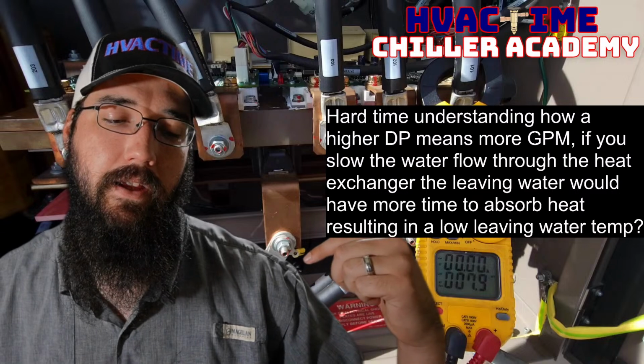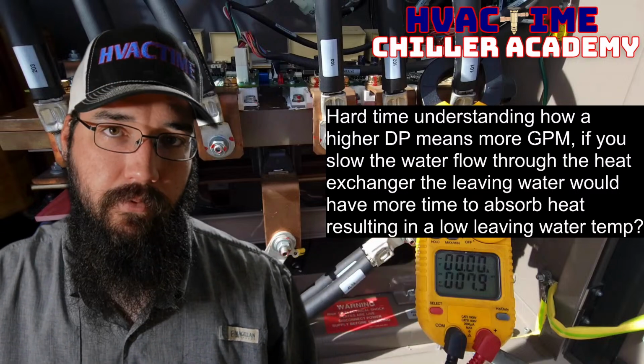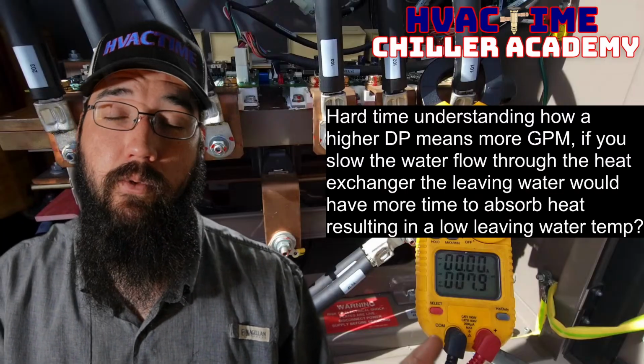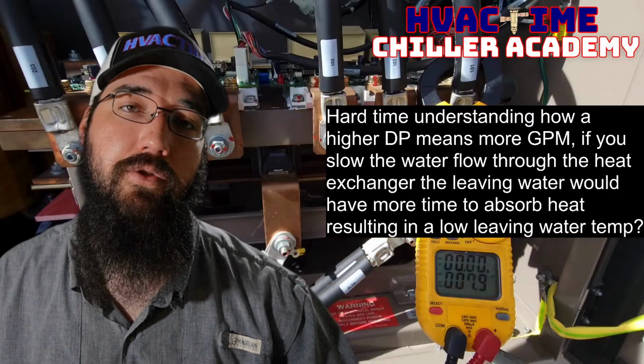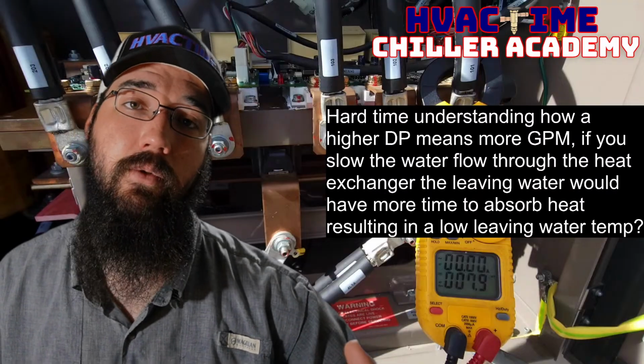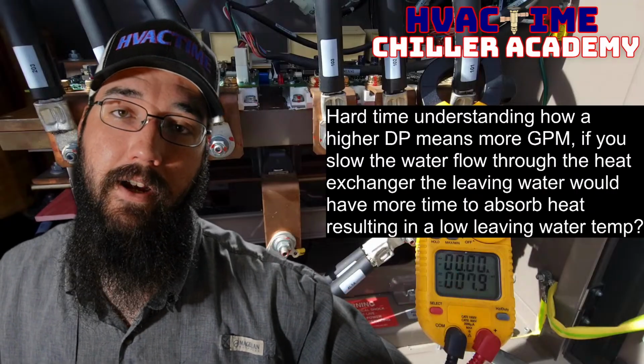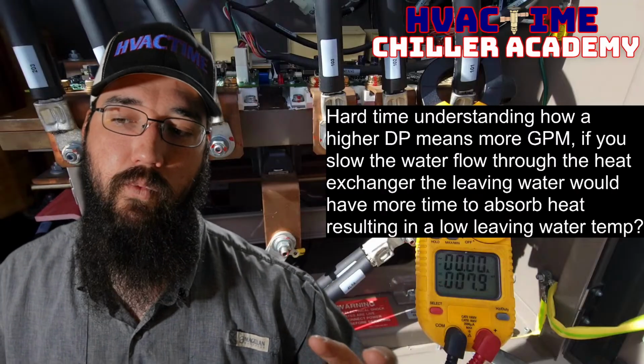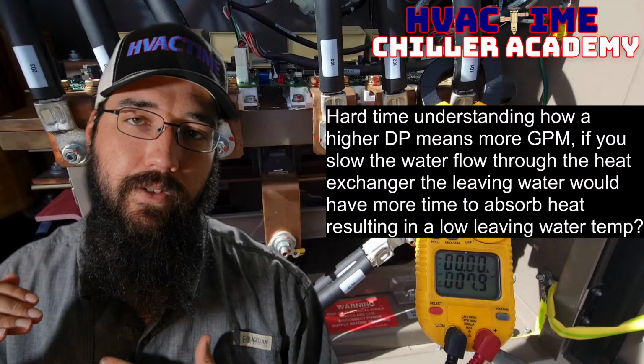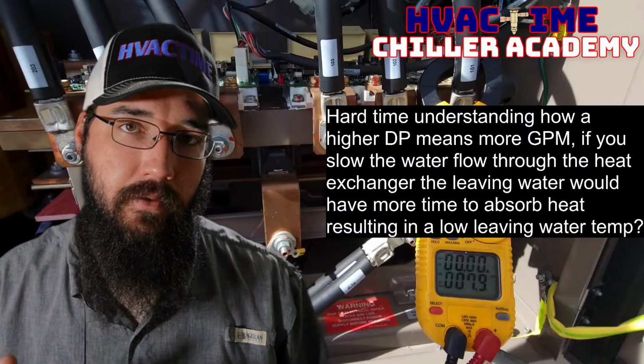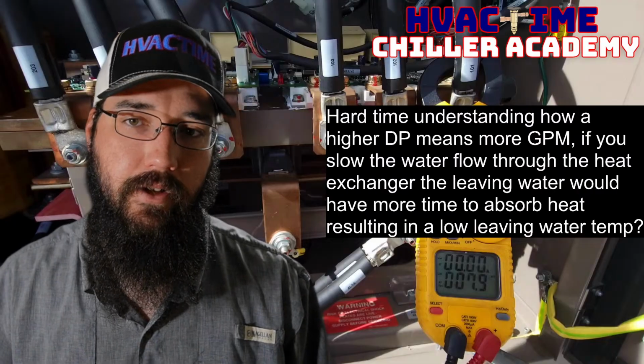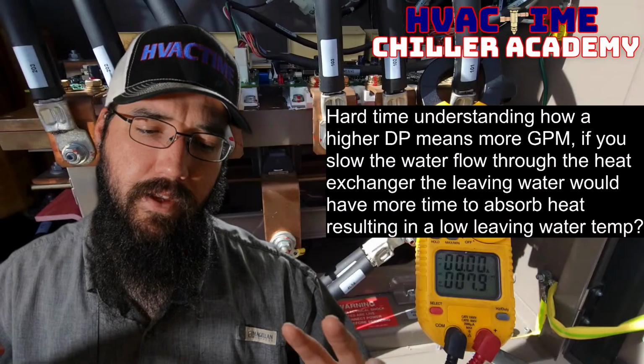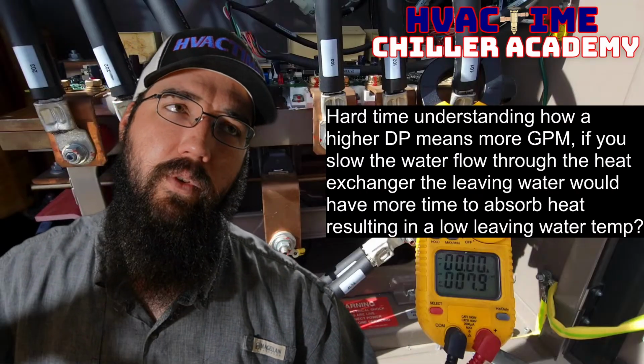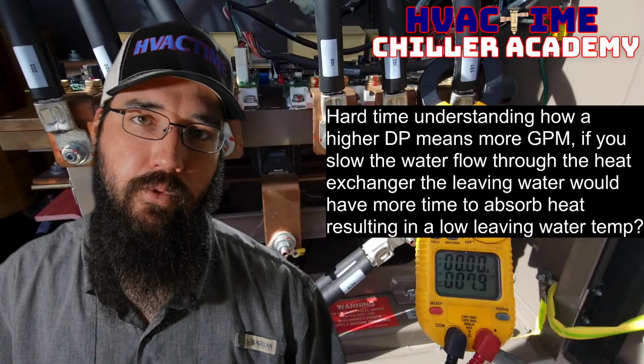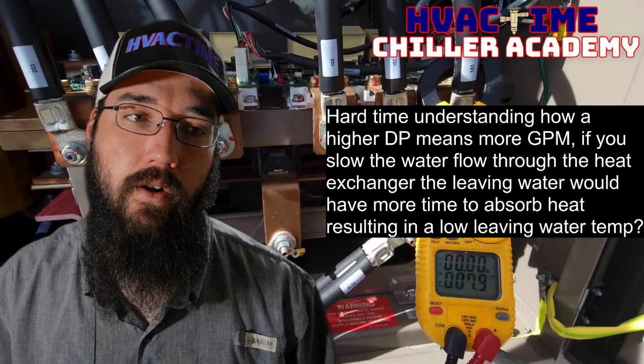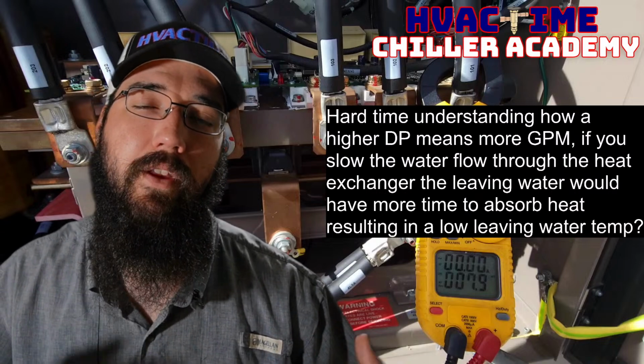What that will also mean, though, is that the whole space, whatever we're cooling, if it's comfort cooling, the building space will begin to get uncomfortable for the tenants. If it is a manufacturing process, we're going to struggle keeping up with the manufacturing equipment. Eventually, that entering water side is going to start to rise and increase, and we'll have higher and higher temperature differences, even though we're technically at design conditions in terms of temperature difference at the chiller. And that could be a symptom of low GPM. So if we're not moving enough flow through the heat exchanger and we're not creating enough differential pressure, we'll hit set point even though we're not actually moving that much heat, just because there is so much contact time with that water. We're able to just draw the heat out of it more than we're actually flowing water through it.